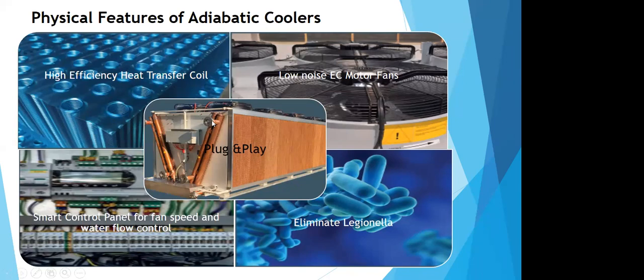And we also get rid of any scaling effect in the circulating water, because of the increased TDS in the case of a traditional cooling tower. Here the water circulates in a closed loop and comes back into the condenser in a closed loop. So virtually there is no treatment required. The water remains clean and isolated from the external atmosphere.